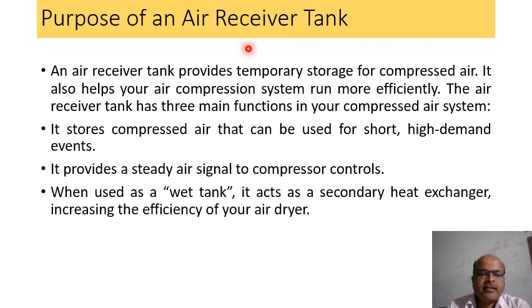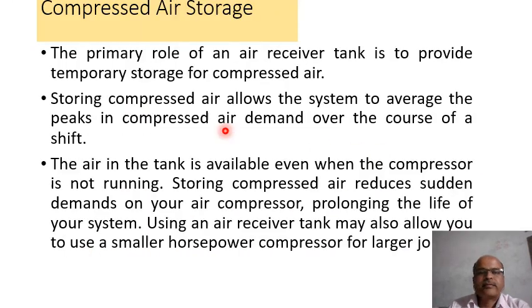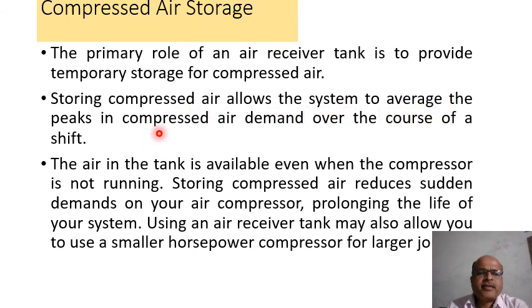Purpose of the air receiver tank: It provides temporary storage for compressed air and helps the air compression system run more efficiently. The air receiver tank has three main functions: it stores compressed air that can be used for short high-demand events; it provides a steady air signal to compressor controls; and when used as a wet tank it acts as a secondary heat exchanger, increasing the efficiency of your air dryer. Storing compressed air allows the system to average peaks in demand, and the air in the tank is available even when the compressor is not running.